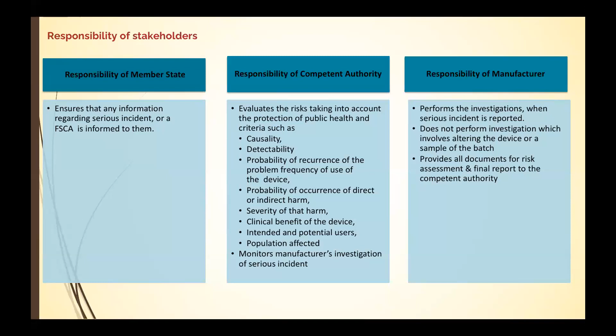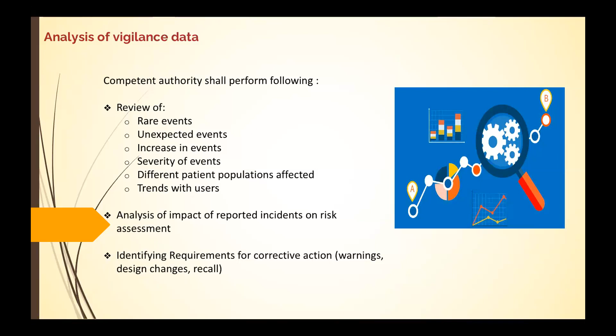As per Article 90, which talks about the analysis of vigilance data, the competent authority shall perform the review of rare events, unexpected events, increase in the events, severity of the events, different patient populations affected, and trends with the users. Also, the vigilance data contains information identifying the requirements for corrective action, warning, design change, or any recall that has happened. So they have to provide the information on the recalls on their websites as well.